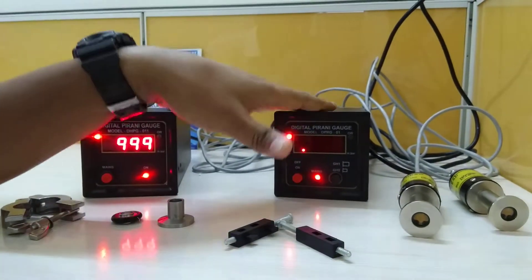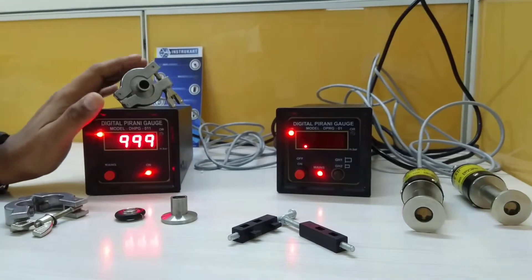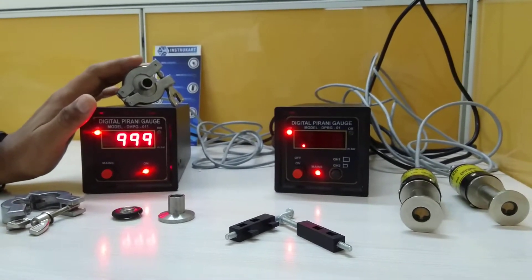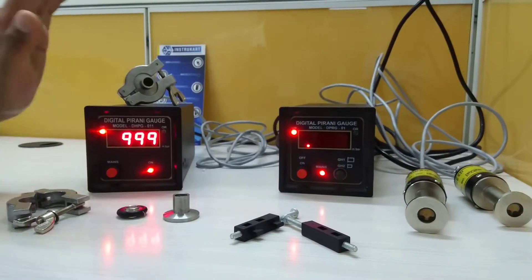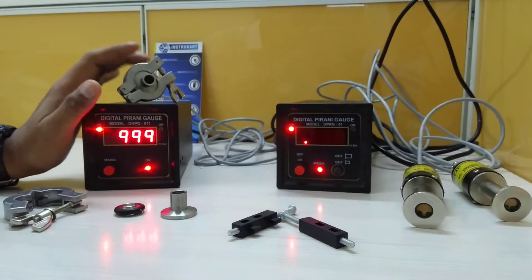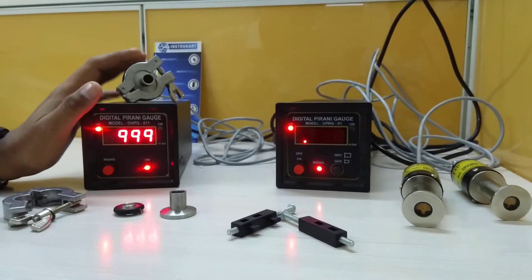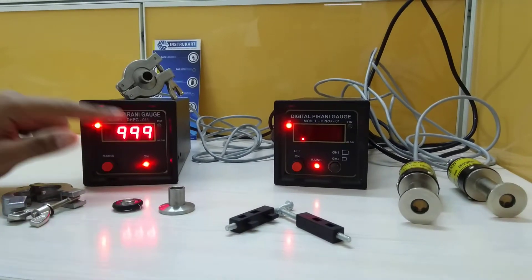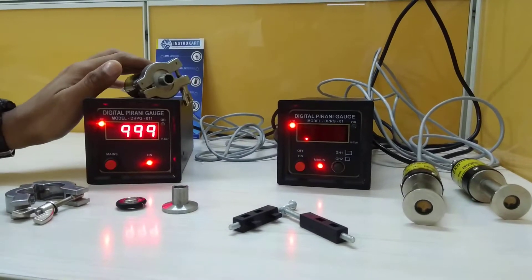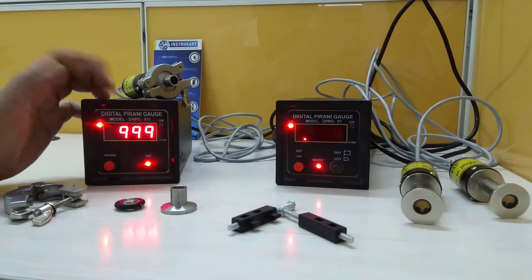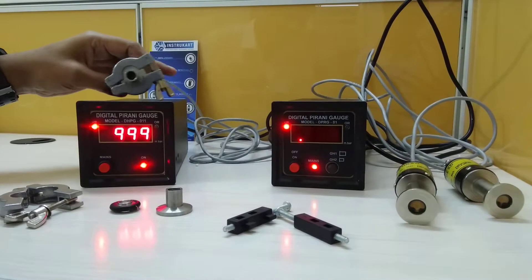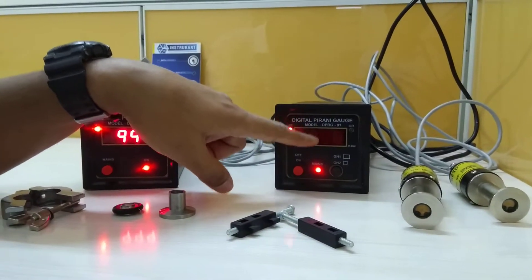This particular gauge is a normal single gauge head Pirani gauge, and this has the range of 999 to 0.001. Now, this 999 is displayed because of the open barometric condition. This display is not visible now because it is not connected to the vacuum pump.